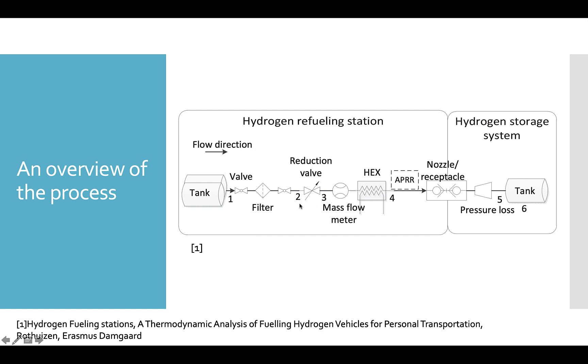The hydrogen is going to pass through a filter and through some tubes, then through a reduction valve where its pressure drops — so the pressure at point 3 is going to be less than at point 2. Then it flows through a mass flow meter, through a heat exchanger where we decrease its temperature, then through a control valve that ensures the pressure just before the vehicle's tank increases at a specified rate for safe fueling. After that it goes through the nozzle where the fueling station ends and the hydrogen enters the vehicle, flowing in until the tank is filled.